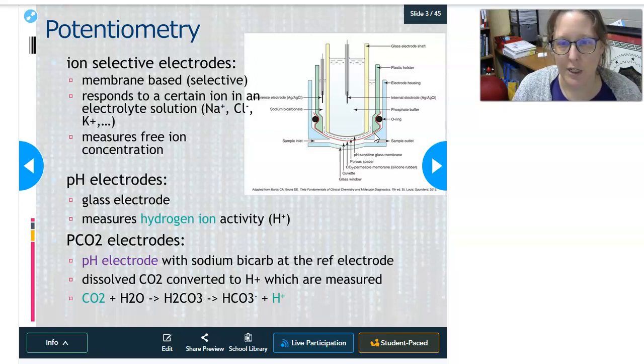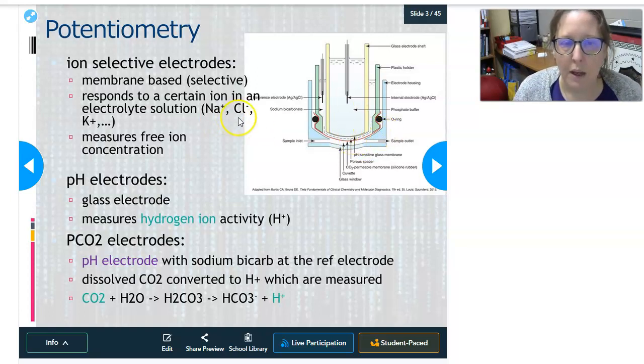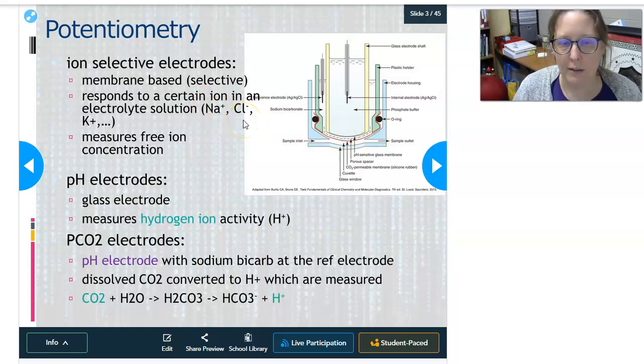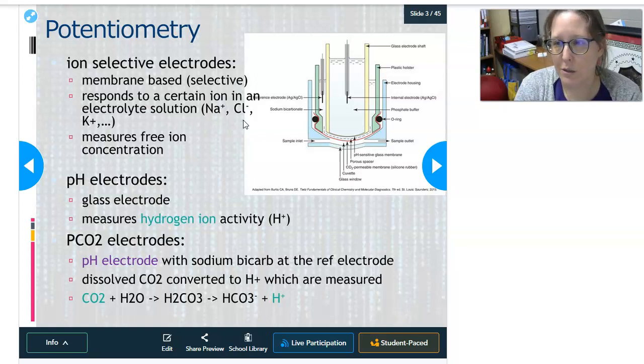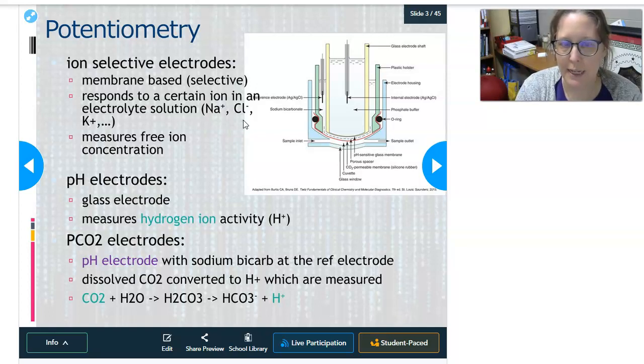What differentiates one electrode from another is usually the membrane and the electrolyte solution. The membrane allows it to respond to a certain ion in an electrolyte solution mix. In serum or plasma, you have a mix — sodium, chloride, potassium, calcium, magnesium, and more. If you want a sodium measurement, you don't want to measure any other ions. They always measure free ion concentration, meaning anything bound to proteins would not be measured.